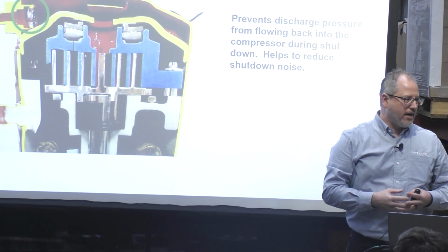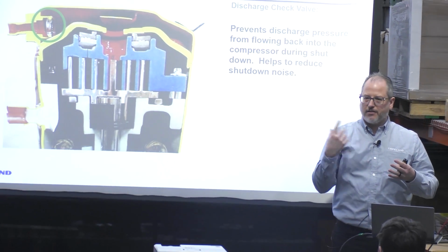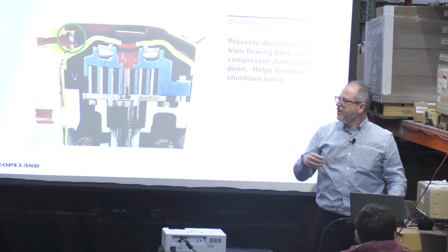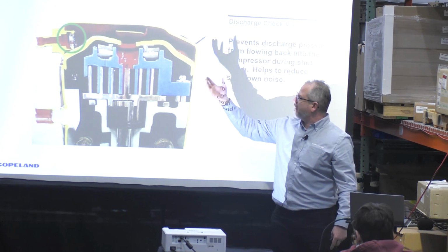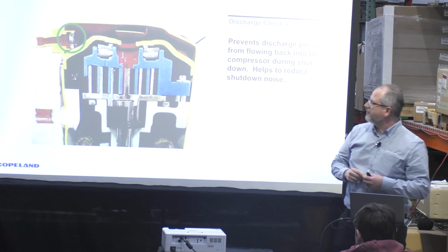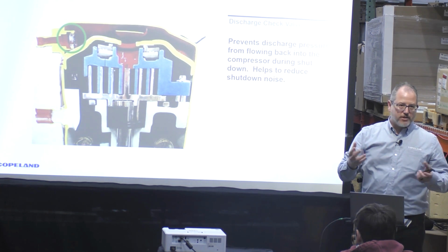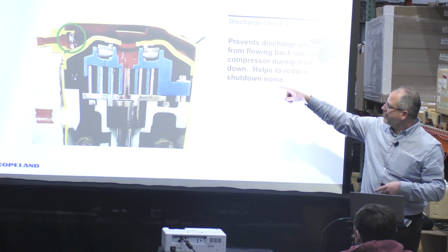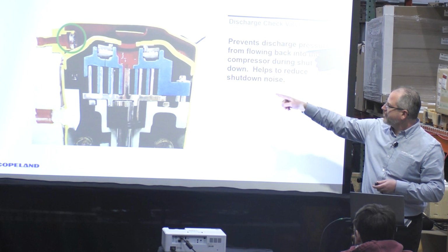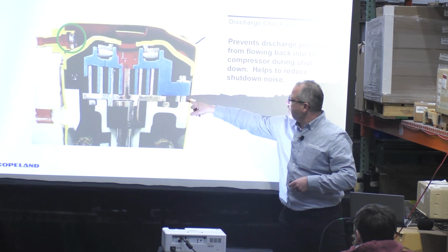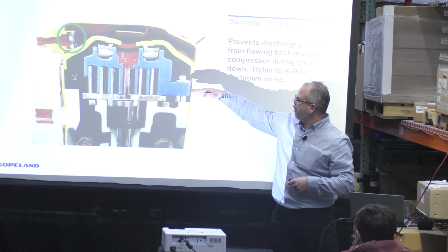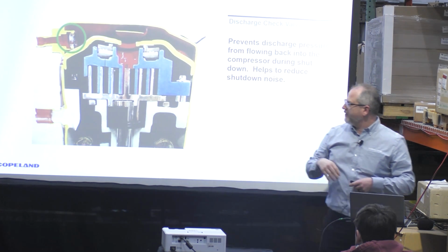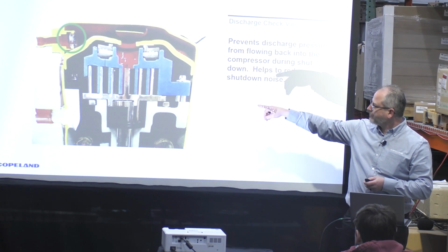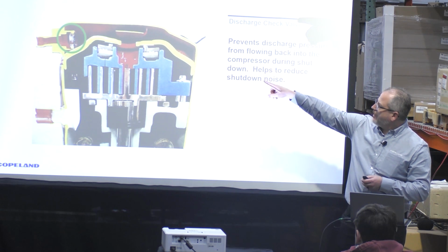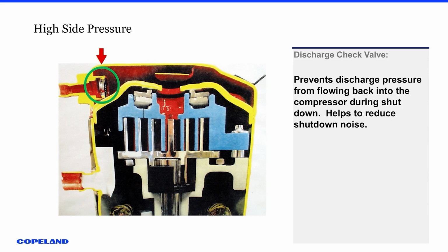And you can see the little hole. So when our compressor's off, and it starts to get the compression process going, it lifts that floating seal up, and then it seals against that muffler plate there. Then when it turns off, the floating seal goes down on those little ridges there. So in this picture, you can see the little sleeve guides for that fixed scroll to lift up that 1 millimeter. In that little circle is our check valve.